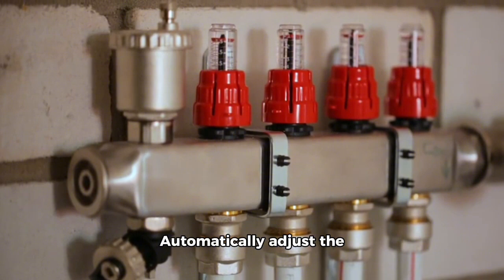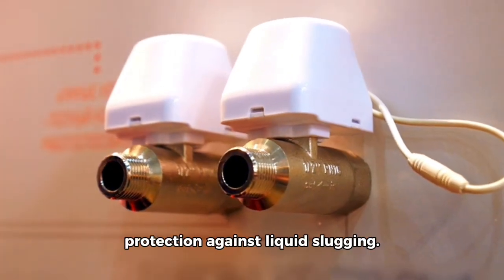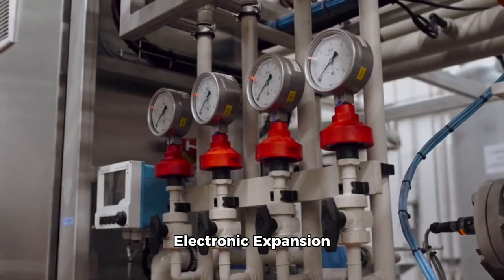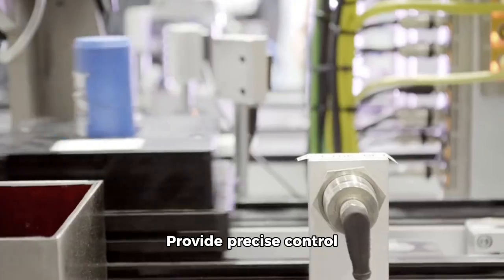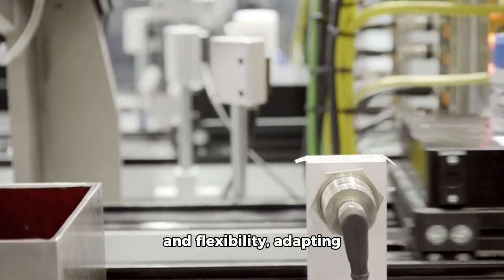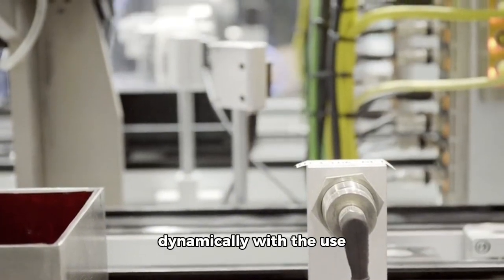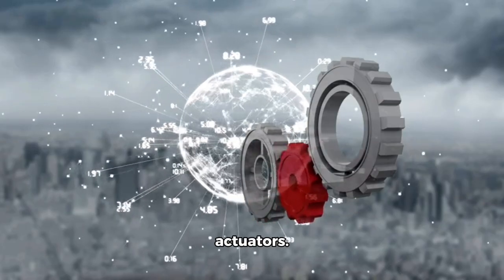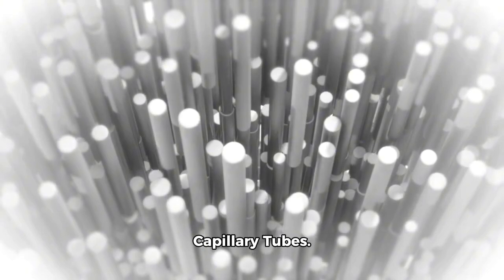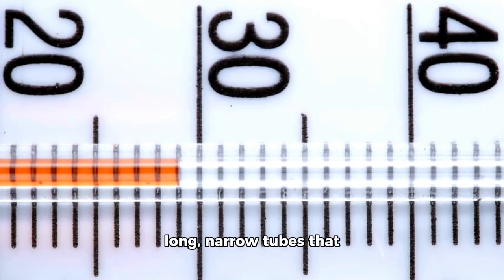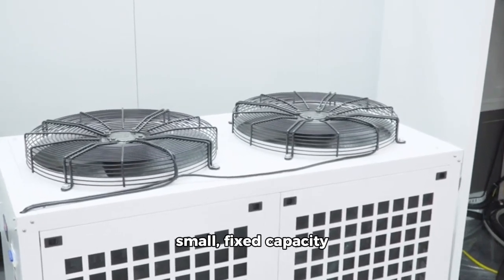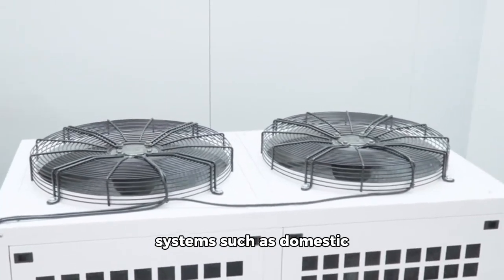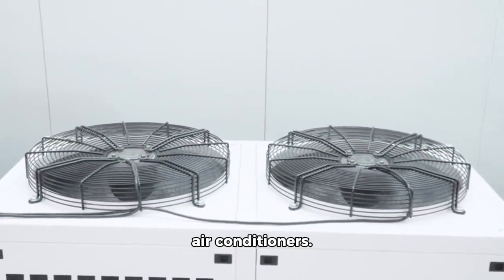TXVs automatically adjust the flow of refrigerant based on the superheat level, offering efficiency and protection against liquid slugging. Electronic expansion valves, EEVs, provide precise control and flexibility, adapting to system conditions dynamically with the use of electronic sensors and actuators. Capillary tubes. Capillary tubes are long, narrow tubes that create a consistent pressure drop through simple passive control. These are most suited for small, fixed-capacity systems such as domestic refrigerators and window air conditioners.